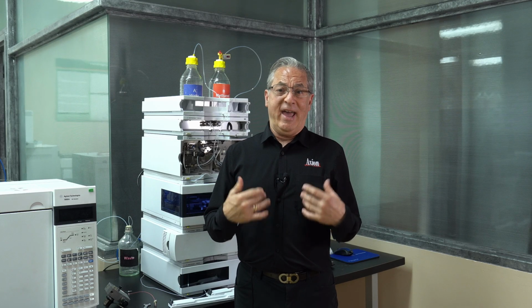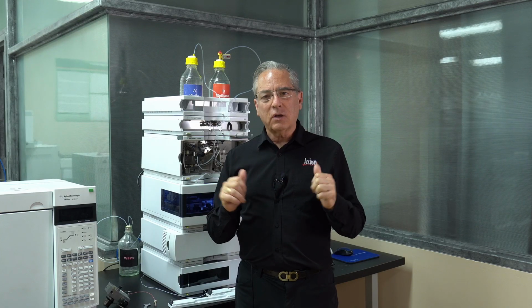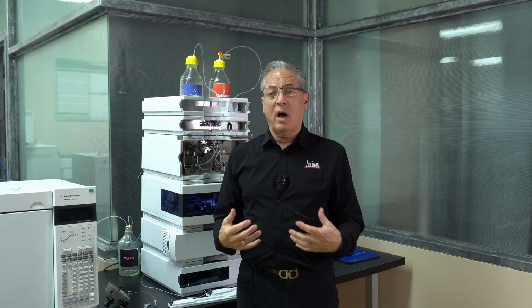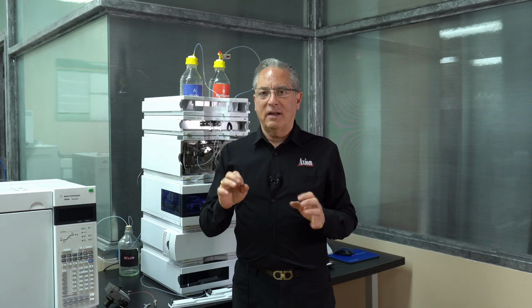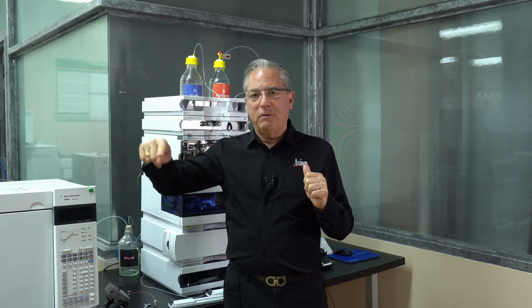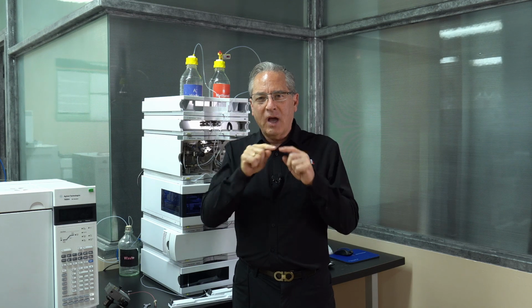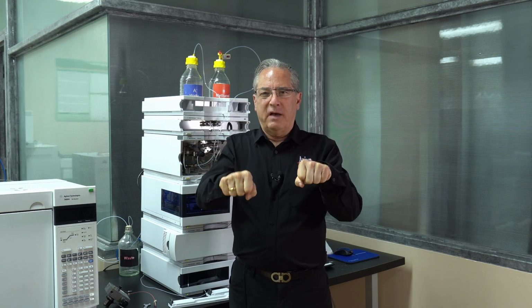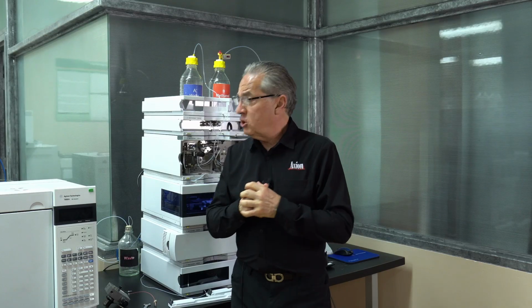It looks like I'm going from 363.5 to 364.5. So I have a 1 bar fluctuation out of a 360 bar pressure. For 360 bar, 2% would be 7.2 bar, so I could bounce plus or minus 7 bar and still be within spec. I'm only bouncing plus or minus 1 bar, which means my pump is in excellent shape. If you look at the pressure trace, you can tell mechanically what's going on with your pump. It should be constant, but on my screen you're seeing that variation. Remember, that is the real pressure in real time going across the pump strokes itself. It's doing exactly what it should be doing, and that fluctuation should be minor.